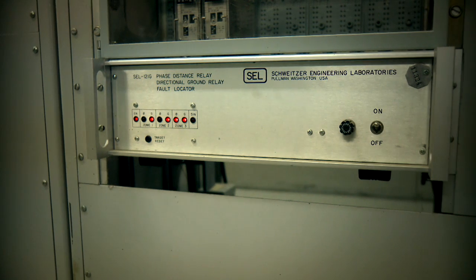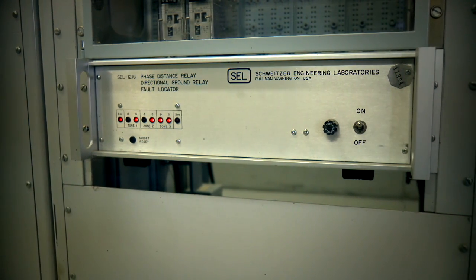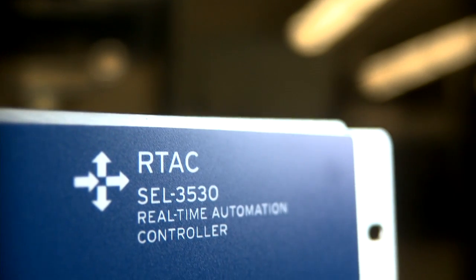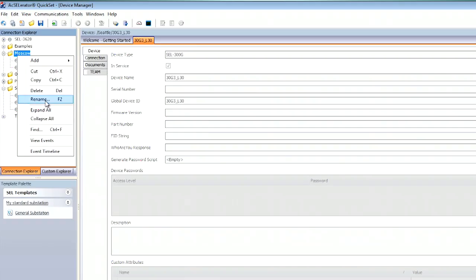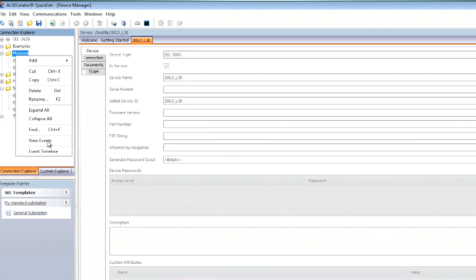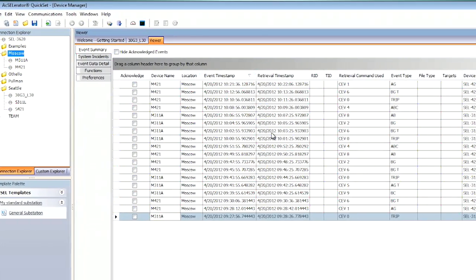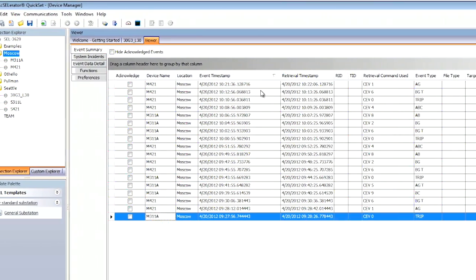We've had event reports in every relay we've ever made. With the RTAC in the substation, you can configure the RTAC to watch for new event reports in every relay it's connected to. If it sees a new one, it will collect and automatically store it locally in static, non-volatile memory. It will then allow the customer to upload those event reports back to a central server through our SEL TEAM software.